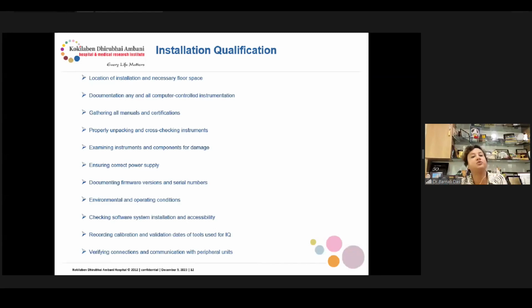For the checklist: the location of installation and necessary floor space, documentation, any and all computer control instrumentation, gathering all manuals and certifications, and then properly unpacking and cross-checking the instrument, examining the instrument and components for damage, ensuring correct power supply, documenting firmware versions and serial numbers, environmental and operating conditions, checking software system installation and accessibility, recording calibration and validation dates of tools used for IQ, and verifying connection and communication with the peripheral units.